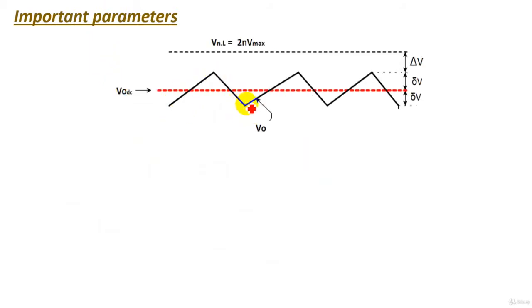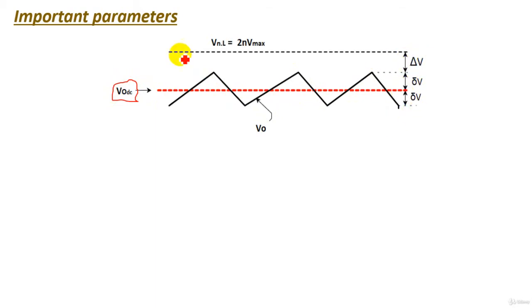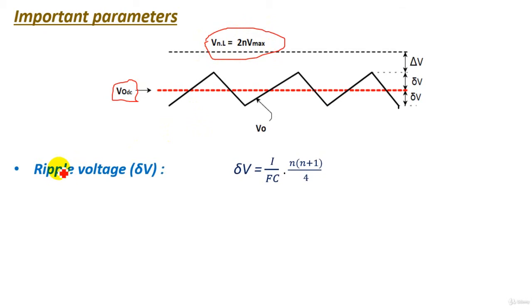Now let's look at the important parameters of the Cockcroft-Walton voltage multiplier circuit. We can simplify the output voltage waveform — this shows the average DC voltage, which is applied to the insulator under test. We also have the ripple voltage, the voltage drop, and the no-load voltage, which equals 2nV maximum — the maximum DC voltage obtainable from the circuit.